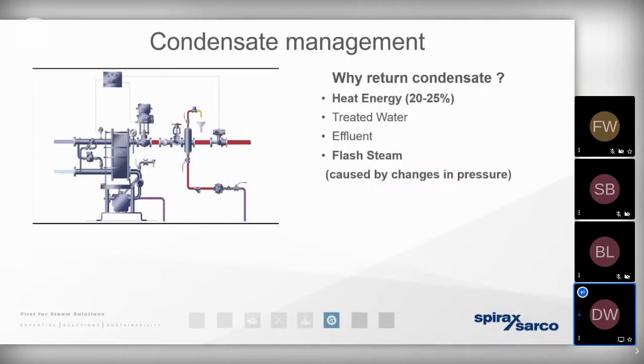The reason being, well, it comes back to the steam tables again. If we look at the steam tables, if we know the pressure and the temperature that that condensate exists at, we know how much heat energy is present within it. It's the sensible heat. And typically that sensible heat, the byproduct of steam when it's given up its heat energy, that sensible heat that's left behind in the condensate, typically is going to amount to 20 to 25% of the total heat energy in the steam.